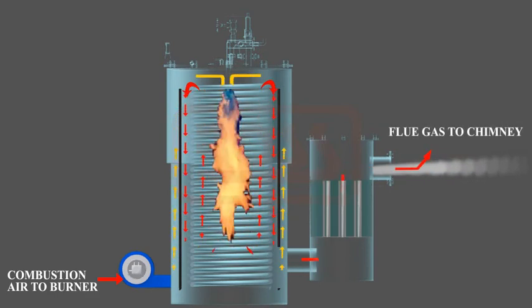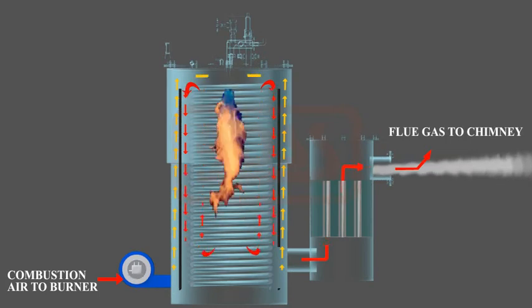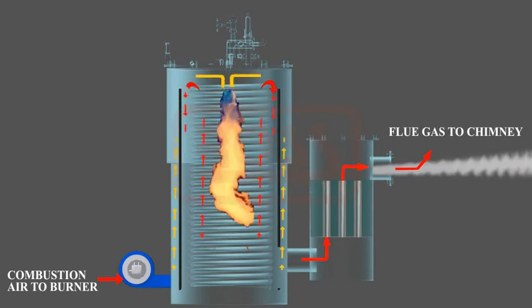Water entering the coil at the bottom is quickly heated up, leading to steam generation in the upper section of the coil. Pressure builds up quickly due to the small quantity of water passing through the coil. When normal operating pressure is reached, the main steam outlet valve opens to supply steam to the process.